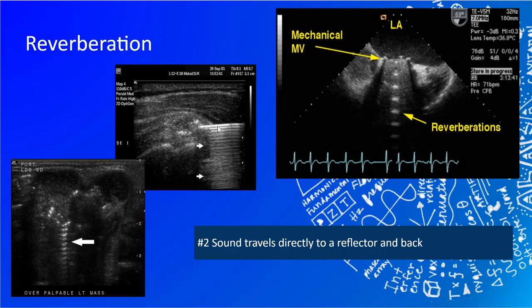It is hitting both of the walls, both of the strong reflecting walls of the needle. So what happens is that sound energy kind of just keeps bouncing back and forth through that needle. And as time goes on, as that sound bounces back and forth through there, a little bit gets sent back to the transducer.